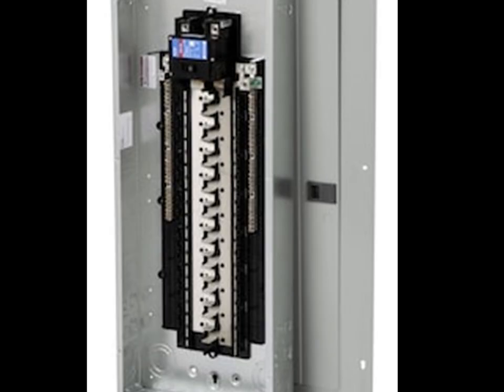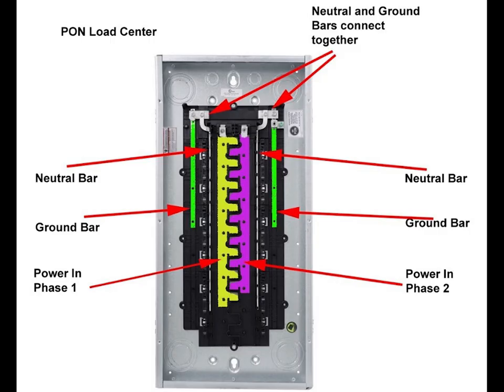Load centers come in 2 types. Some have plug-on neutral, PON, and some do not. The load center depicted here is a plug-on neutral load center. Plug-on neutral means that the circuit breakers have 2 electrical connections in each breaker, a power connector and a neutral connector. Connections in your plug-on neutral load center.